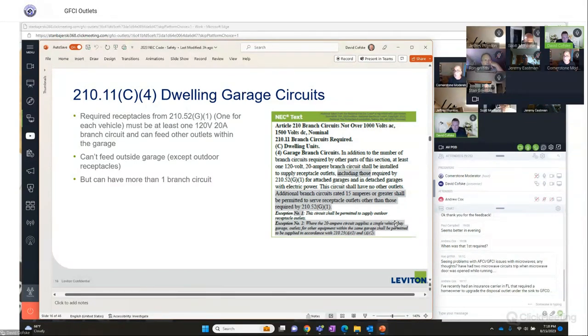Basements and garages need to be GFCI protected. This article just talks about if you have a GFCI device in your garage, you can use it. You can come out of your garage for an outdoor receptacle, but you just can't run that circuit anywhere else other than to a receptacle on the outside of the house.